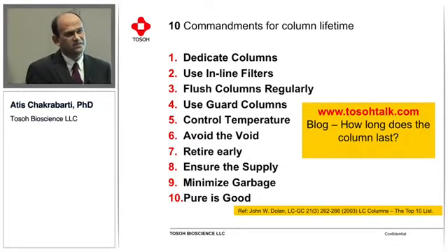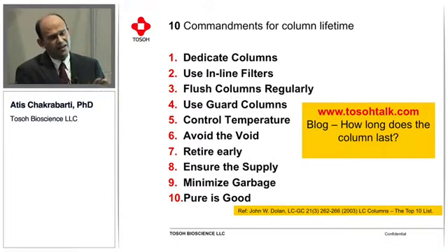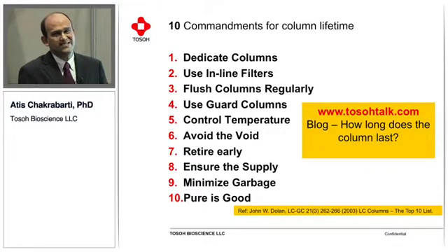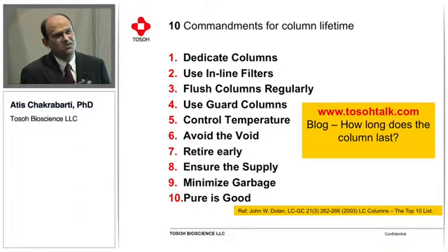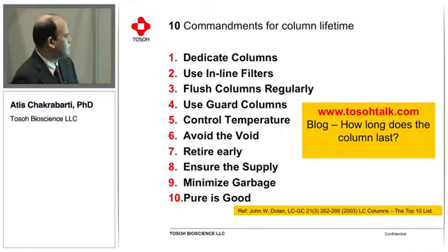We always encourage the end users and scientists to please use the guard column, because the guard column helps in trapping all those dirty materials from entering into the column. And whether your column is now under pressure from the dirty materials or not, you can figure it out just by the change in the back pressure in the system.